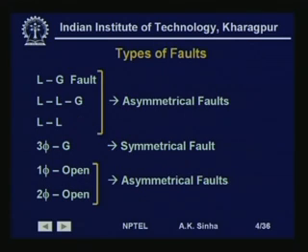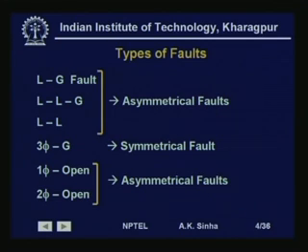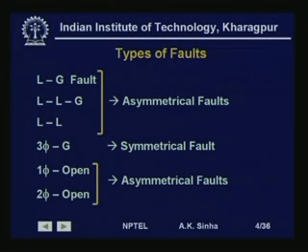As we discussed earlier, the most common fault which occurs is the line-to-ground fault. The next most common are line-to-line-to-ground, double line-to-ground, or line-to-line faults. These three faults are much more common than three-phase-to-ground faults and are basically asymmetrical faults, because they create asymmetry in the current and voltage in the three phases of the system. A three-phase or three-phase-to-ground fault is a symmetrical fault because the current and voltage symmetry in the three phases are maintained.